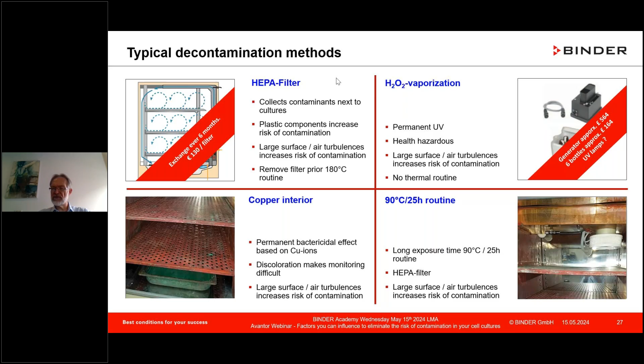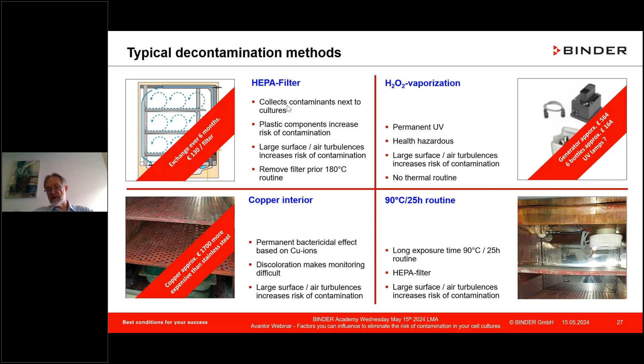And this basically is also an issue. A HEPA filter, 130 pounds, must be exchanged every 6 months. Then you have the generator right here with the 564 pounds. The bottles, 6 bottles of hydrogen peroxide, 164. UV lamps, not quite sure, probably around 300, 400 British pounds. Copper is always expensive, more expensive than stainless steel by raw material, somewhere around 1,700 euro more costly than a stainless steel. And these are things that definitely a purchasing department should have an eye on.